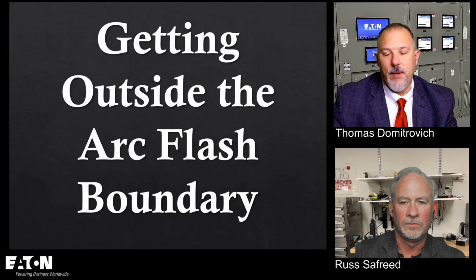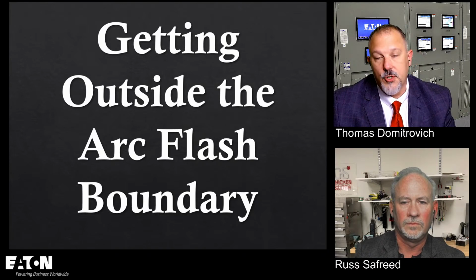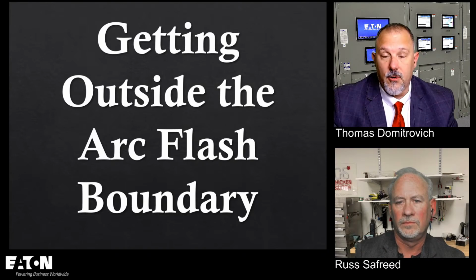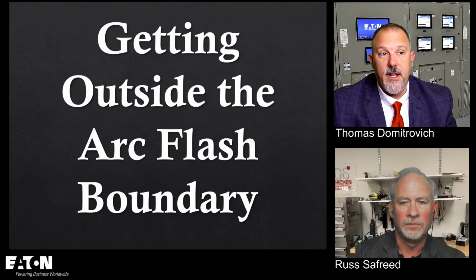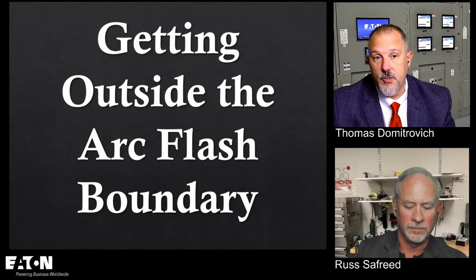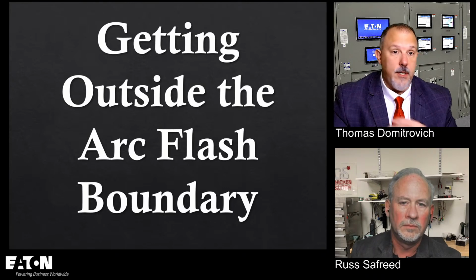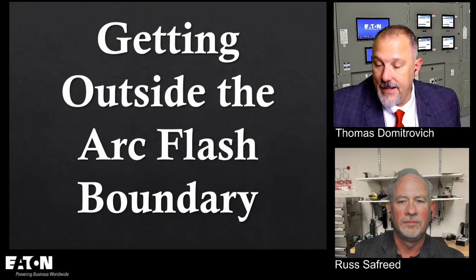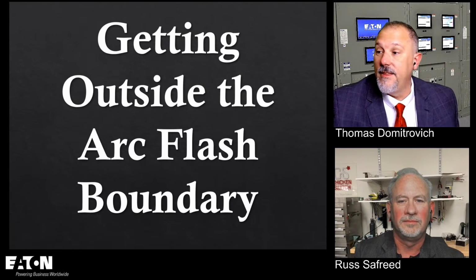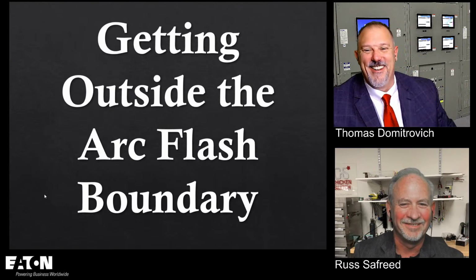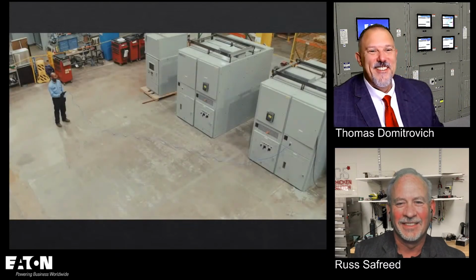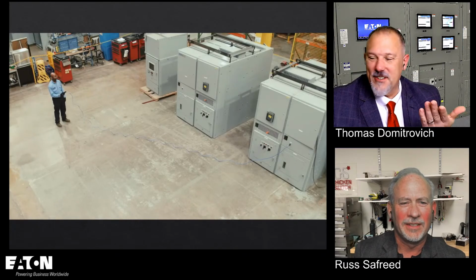When we do a lot of educating about short circuit current ratings and interrupting ratings - if you exceed the short circuit current rating of an upstream piece of equipment, the current passing through it becomes an unintended rapid disassembly in the field. Yep, and there's your arc flash boundary.